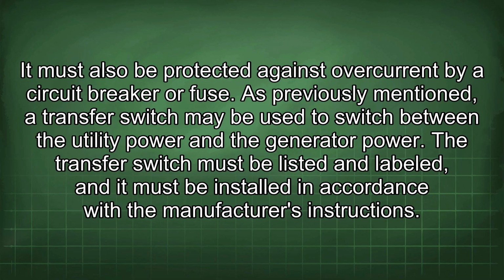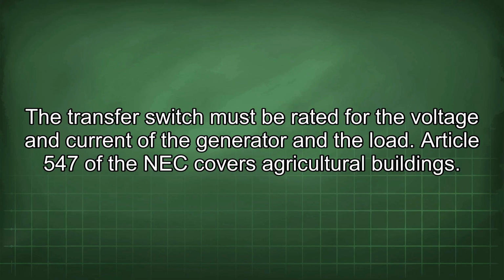As previously mentioned, a transfer switch may be used to switch between the utility power and the generator power. The transfer switch must be listed and labeled, and it must be installed in accordance with the manufacturer's instructions. The transfer switch must be rated for the voltage and current of the generator and the load.